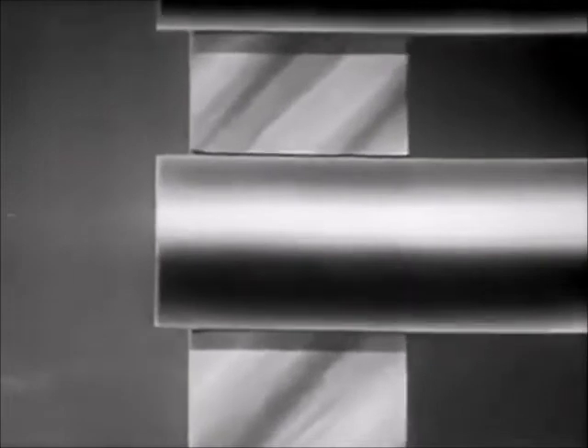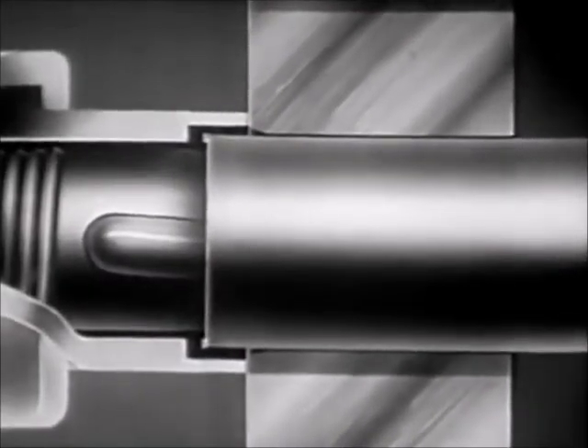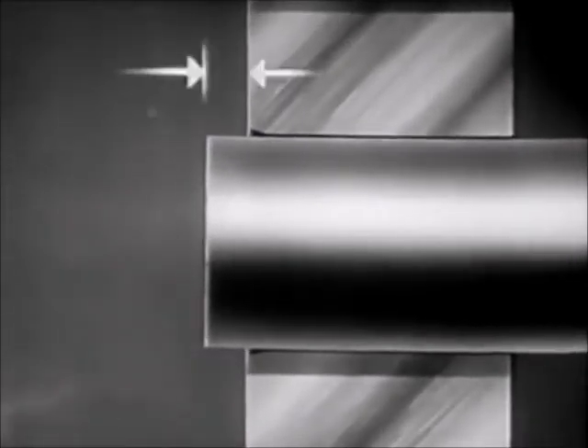If these ends are to be expanded, don't forget to use a recess collar, which clears the tube ends. Outflow ends are not flared and may extend beyond the tube sheet up to about 1/16 inch. If there are a large number of tubes to be expanded at the outflow end, do small groups spaced to equalize the strains and stresses in the tubes and tube sheet.